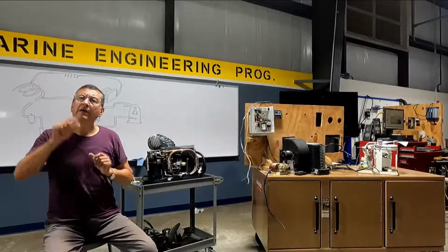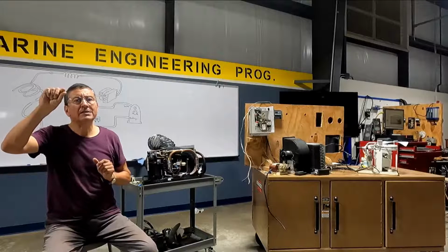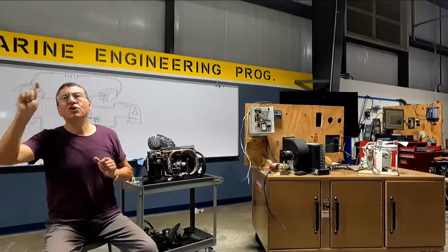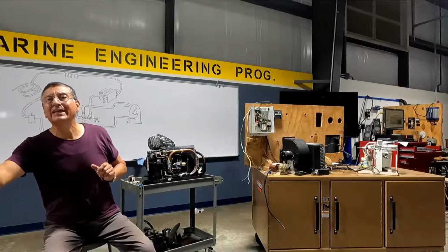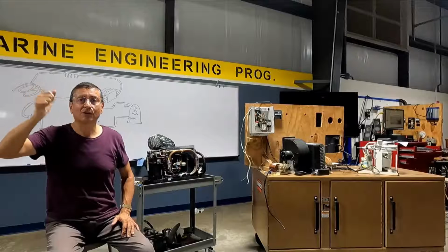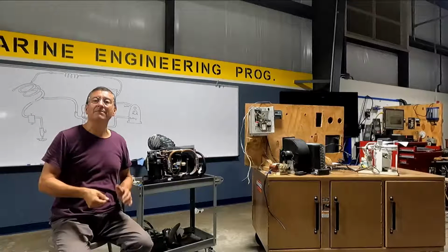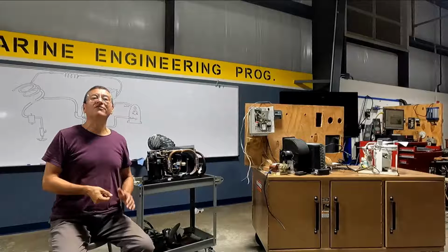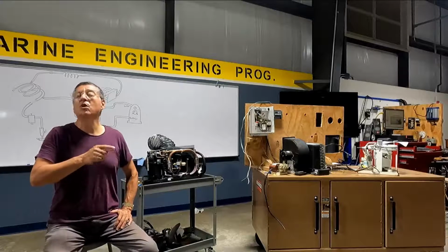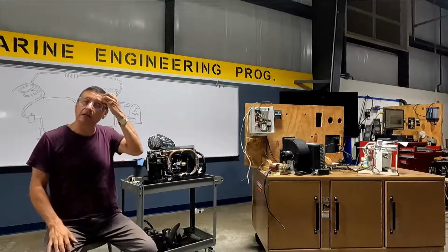What happened if the output of the compressor enters not in the outdoor coil? The discharge of the compressor with high pressure and high temperature enters in the bottom of the evaporator, which is too hot, and when the air passes over there, I receive hot air.